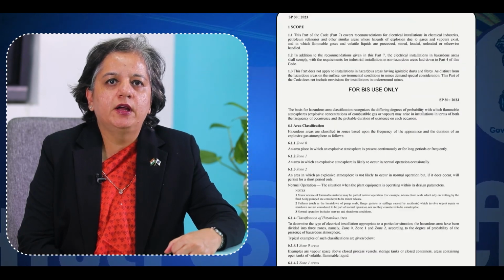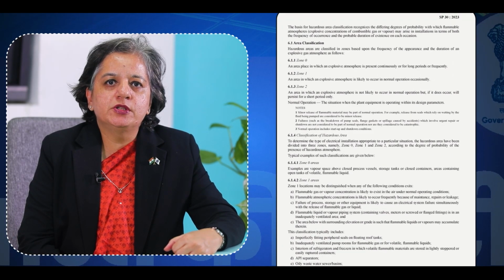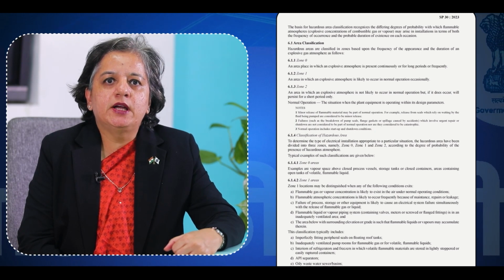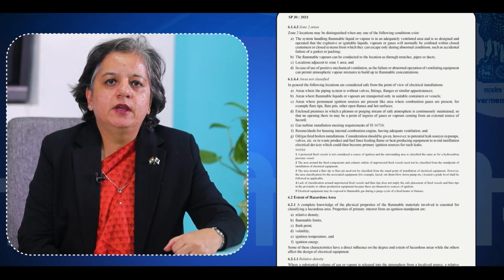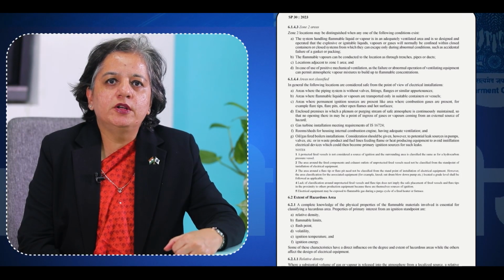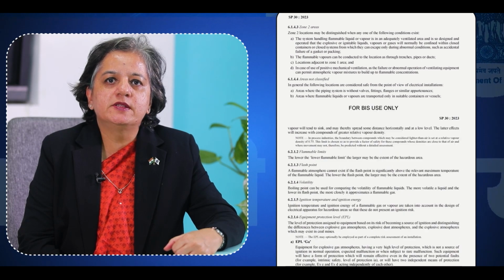It is recommended that plants and installations in which flammable materials are handled or stored be so designed that the degree and extent of hazardous areas are kept to a minimum. Similarly, consideration should be given to design and operation of process equipment to ensure that even when it is operating abnormally, the amount of flammable material released to the atmosphere is minimized in order to reduce the extent of hazardous area. To determine the type of electrical installation appropriate to a particular situation, the hazardous areas have been divided into 3 zones, namely Zone 0, 1 and 2, according to the degree of probability of presence of hazardous atmosphere.